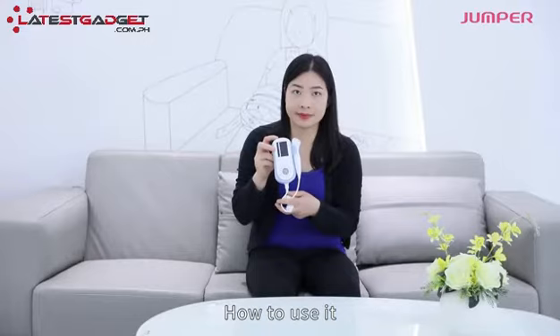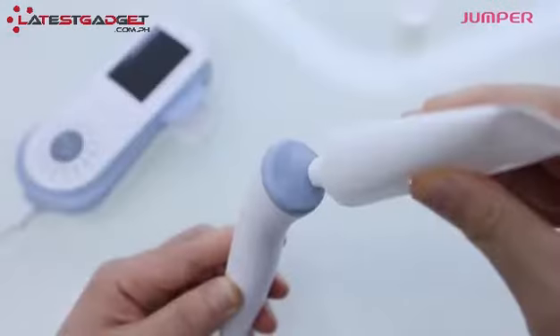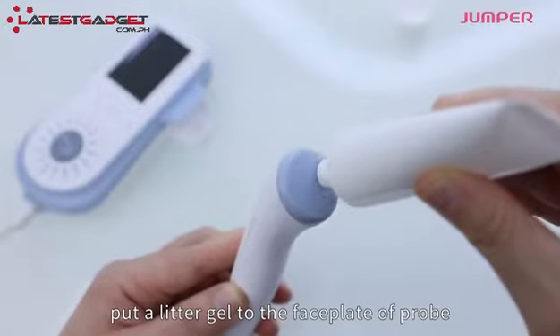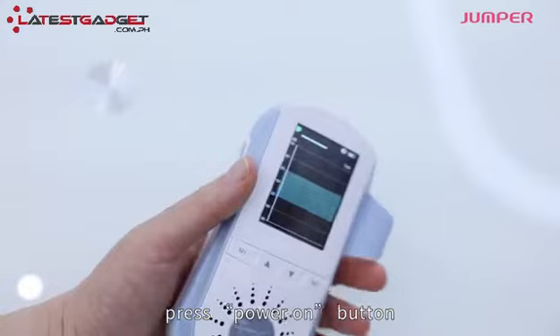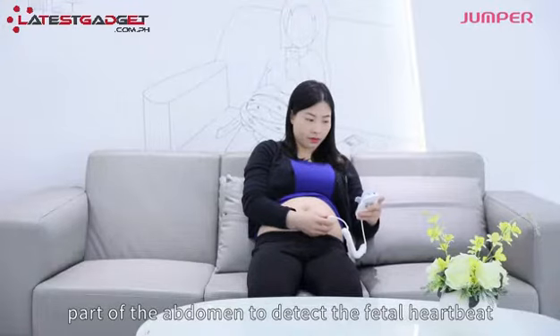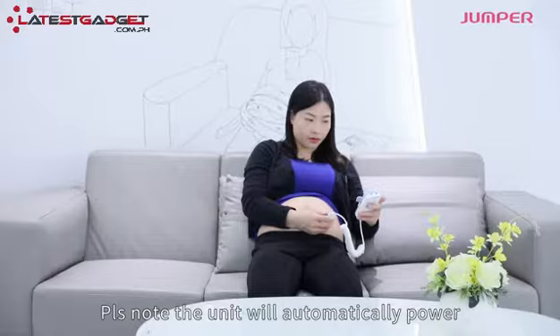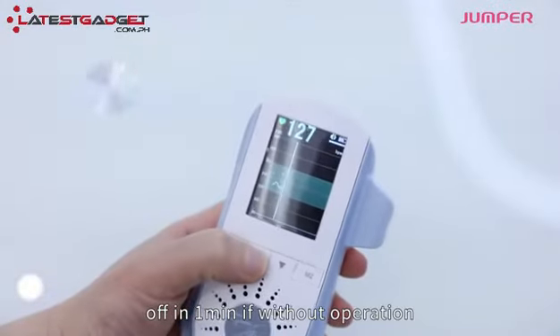How to use it, please follow me. Put a little gel to the faceplate of the probe. Press the Power On button. Then, move the transducer slowly over the lower part of the abdomen to detect the fetal heartbeat. Please note, the unit will automatically power off in 1 minute if without operation.